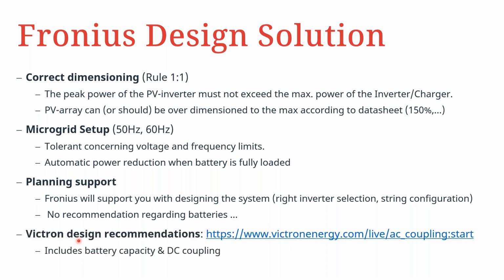If you go to the Victron website, I've put a link here that you can also follow. This tells you, in terms of the battery capacity, depending on the total capacity of the PV array as well as the connected inverter chargers, what is the desirable kilowatt hour in terms of the battery capacity. And if you also want to DC couple some MPPTs, it shows what the design or sizing considerations are for that as well.